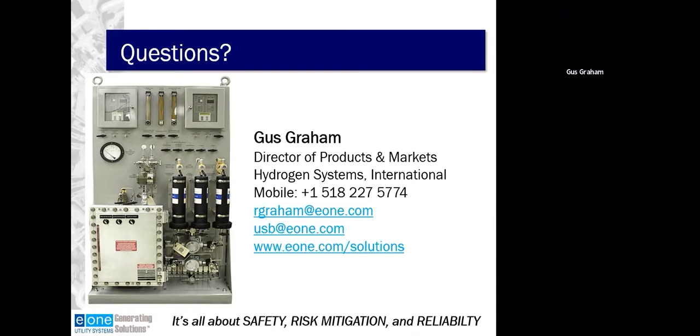The part number may be different, but it's form, fit, function identical. The second question is the life. We would expect the life of the purity cell to be between 5 and 10 years as a normal expected life. We've got some machines that have been operating 10, 15 years with the same cells, working just fine.